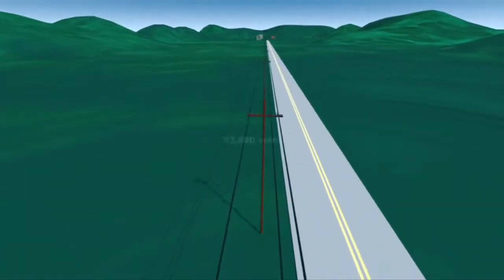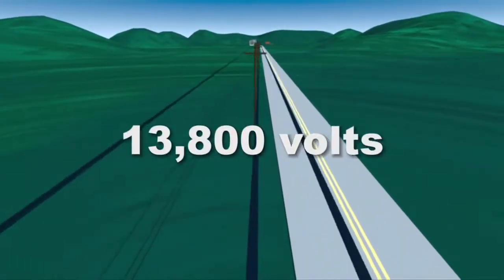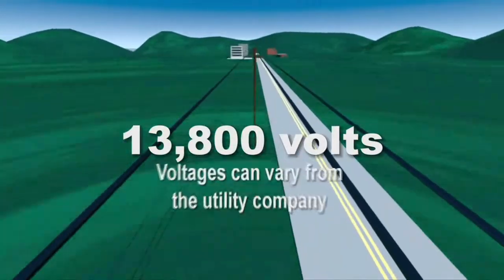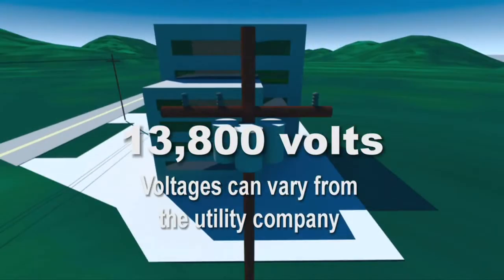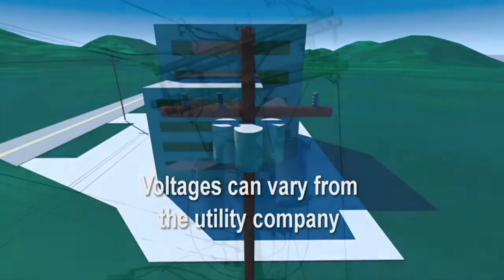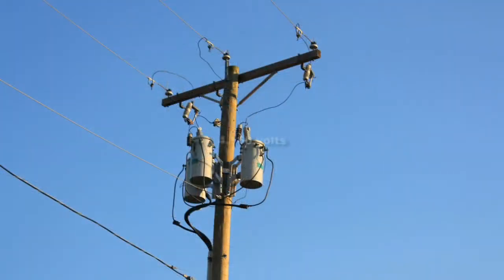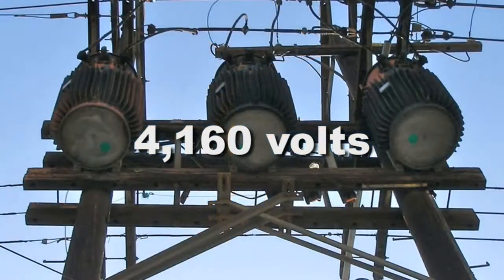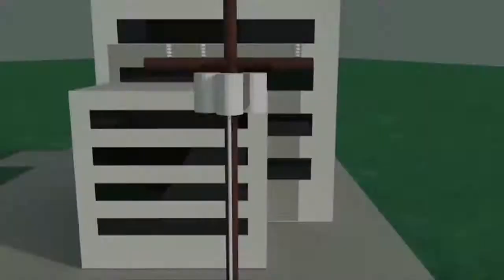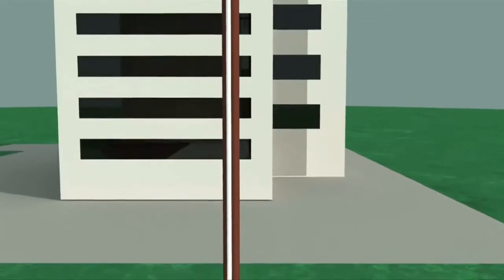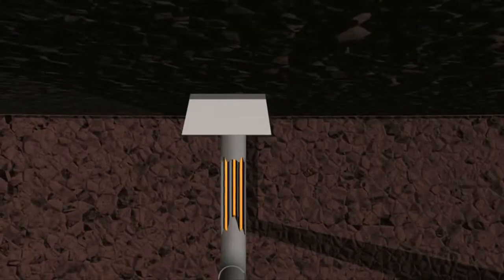In our example, we begin with the utility company supplying 13,800 volts from the road to a utility pole in the parking lot. At the top of this pole, you see three transformers. These transformers will step down the 13,800 volts to 4,160 volts. This voltage is transferred down the pole through copper wires that are encased in conduit.